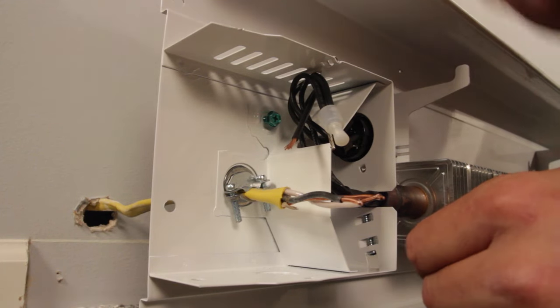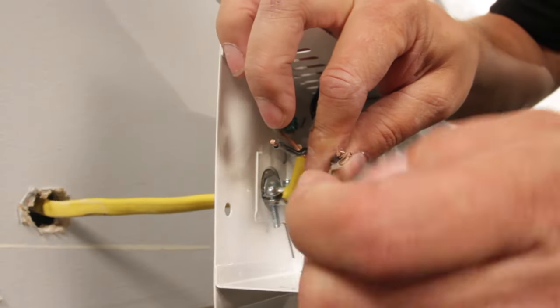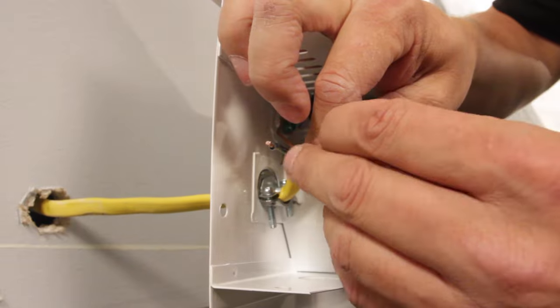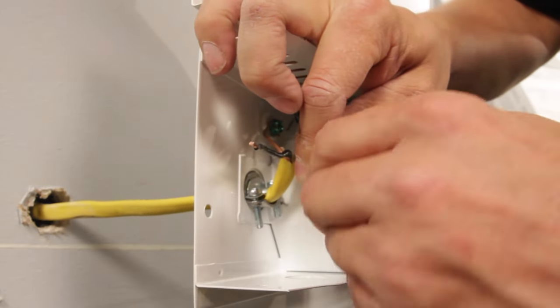Now you're actually ready to wire the heater. Attach the bare copper wire to the green ground screw and tighten it clockwise. Take the white supply wire coming from the wall and attach it to one of the black wires in the heater.